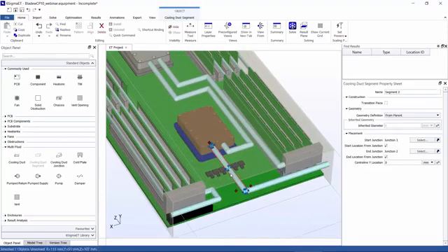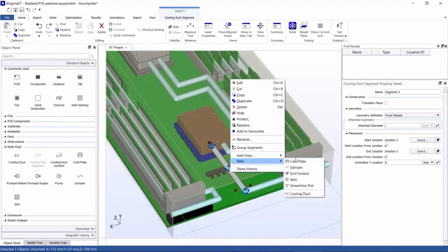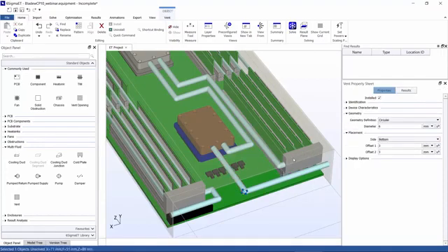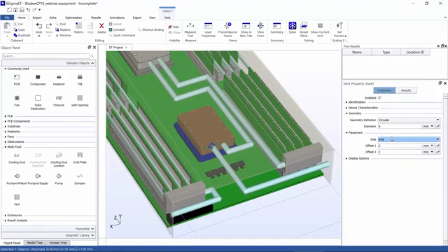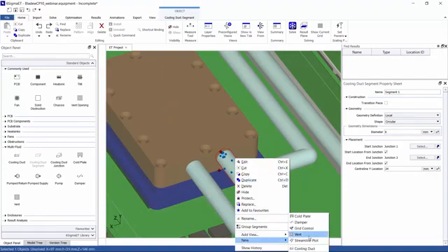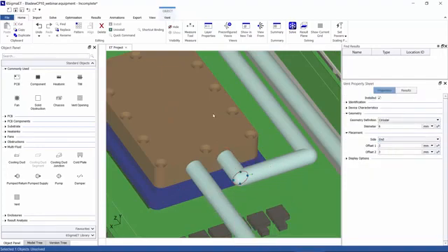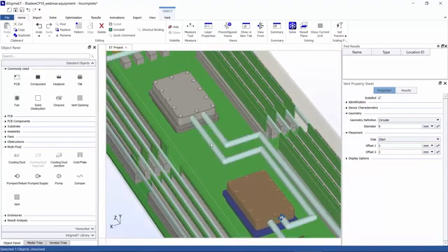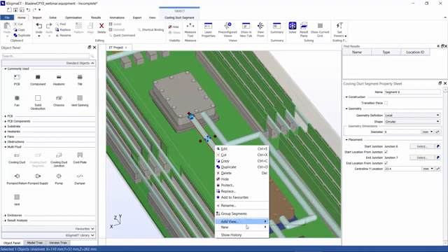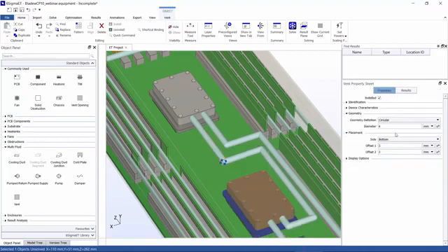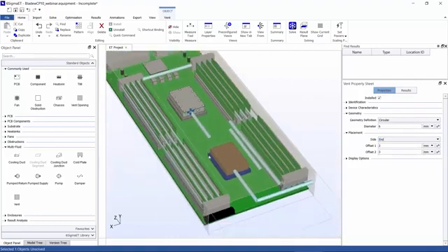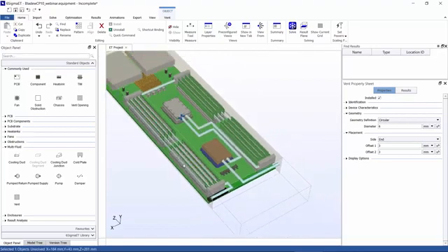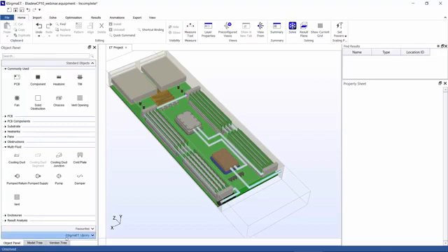My final step here is to add vents to these ducts. I can do that by right-clicking on those cooling ducts and then add a vent and just apply it to the end of the cooling duct. This is important to add before going on to the solve, so that flow will be allowed to go through these cold plates. There we go. So that's it, that's a simple preview on how to build up a liquid cooling model in Six Sigma ET.